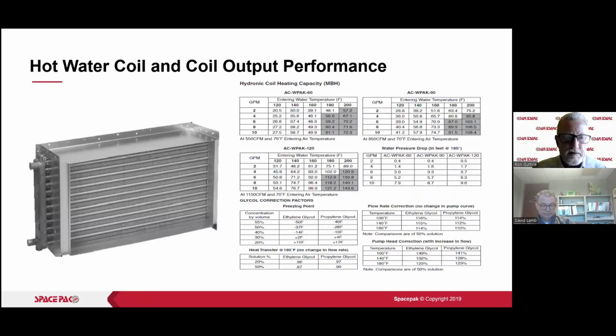All right, water coil performance. The easiest way to know what you can get out of these, how much heat am I going to get out of the small, the medium, or the large, the 60, the 90, or the 120. Well, the amount of heat is going to be 60, 90, or 120. Okay, and they are used on the 60s, used on the smaller air handler, the 90s used on the medium air handler, and the 120s is used on the large 4 and 5 ton air handler. That rating is right in here, about 8 GPM at 180 degrees. You would revert to this chart if you're going to vary from that. But just determining how much heat you'll get, you would use that nominal 60, 90, or 120 model number.